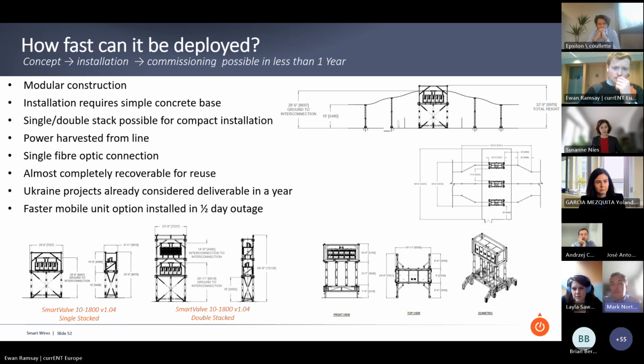It needs a concrete base at the bottom, a simple support structure like most items of plant and equipment in a substation. We can single and double stack, so again we reduce space needed — we don't need extra land. The devices draw all the energy they need from the line, so the only other thing needed is a single fiber connection coupling the units together for control, and virtually all of the equipment can be recovered.